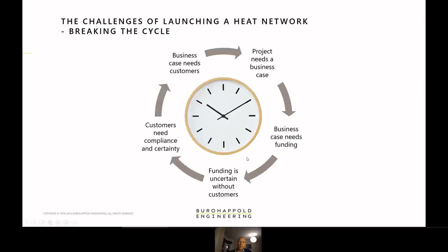So what did our analysis turn out? It turns out that ground source heat pumps and systems are inherently more expensive than the counterfactual, so it's a high cost system. As we take CHP out of the equation, we remove electricity revenues, which leaves operational viability gaps, which makes RHI, or an incentive to enable heat, absolutely essential to give any sort of acceptable returns in the UK. So for this particular project, RHI makes the scheme investable.